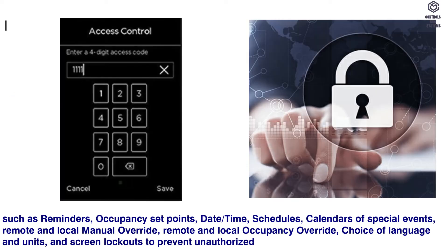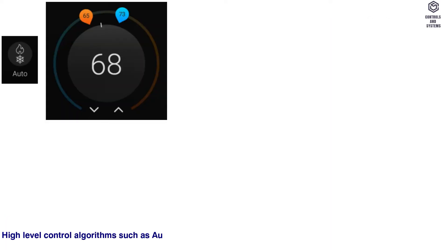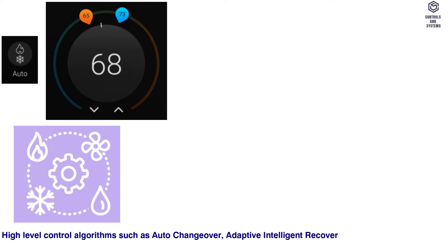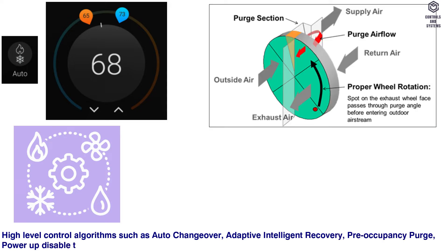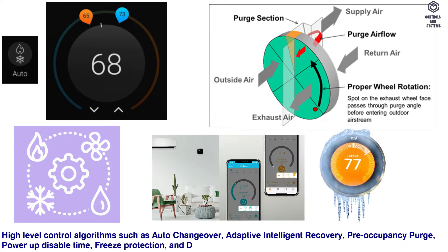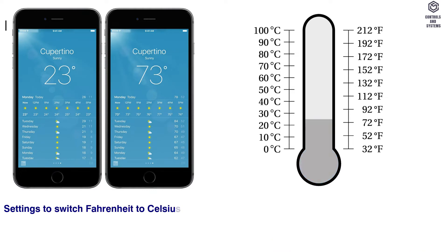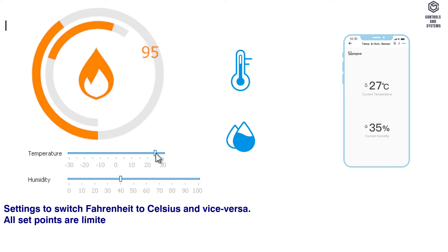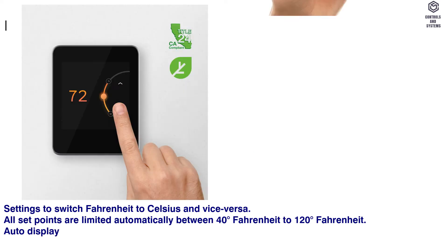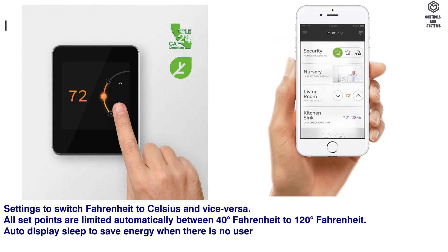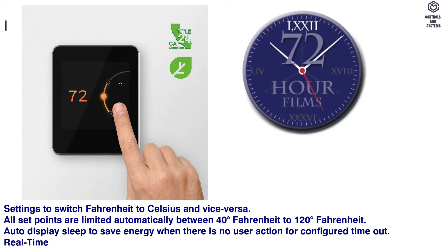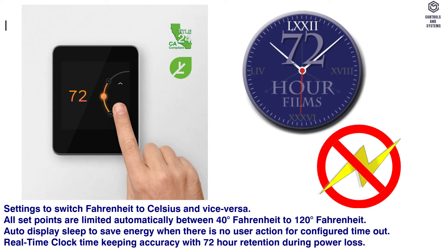Features include choice of language and units, and screen lockouts to prevent unauthorized settings changes. High-level control algorithms such as auto changeover, adaptive intelligent recovery, pre-occupancy purge, power-up disable time, freeze protection, and demand limit controls are supported. Settings to switch Fahrenheit to Celsius and vice versa are available. All set points are limited automatically between 40 and 120 degrees Fahrenheit. Auto display sleep saves energy when there is no user action for a configured timeout. Real-time clock timekeeping accuracy with 72-hour retention during power loss.